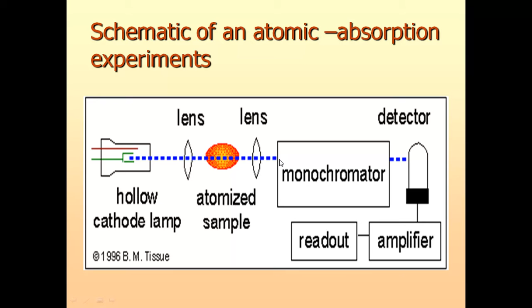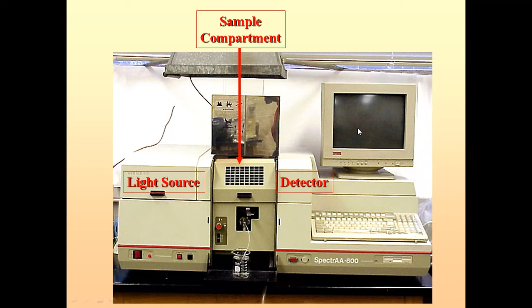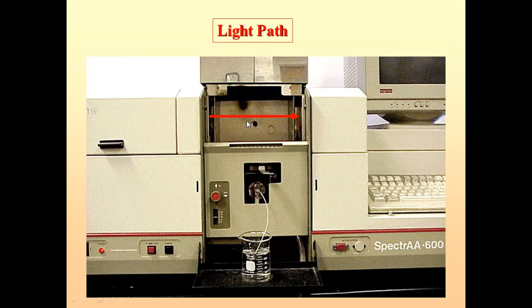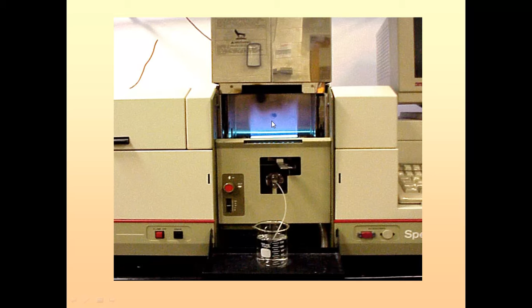Through the capillary the sample is sucked, and then it goes to the atomization chamber. This is basically the heart of the instrument. Then we are using two gases, acetylene and air, which give the flame. From this flame the sample gets to the excited state, and these vapors are detected by the light, which passes through the detector. Whatever the readout is, we get it on the PC. So this is the light path. In this chamber there is a flame, and the sample gets sucked in. If a blue tinge is there, it means the metals are not there. If some yellow is there, that indicates an increase in concentration.